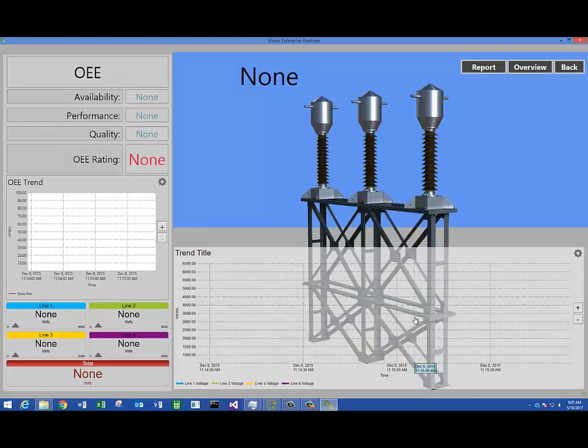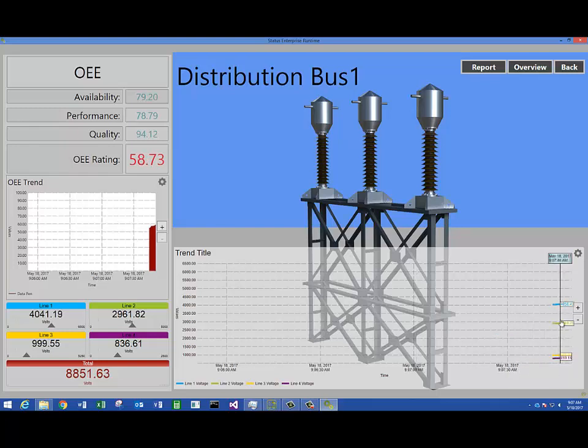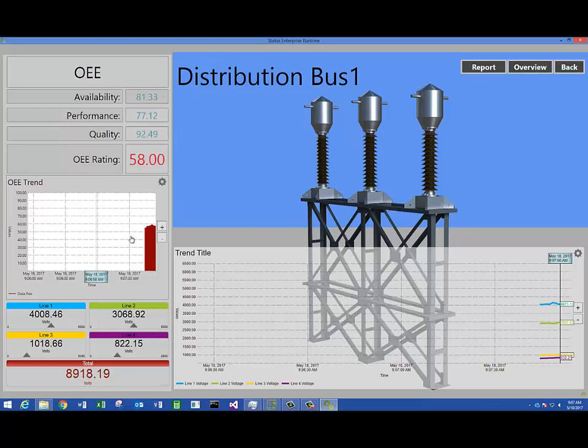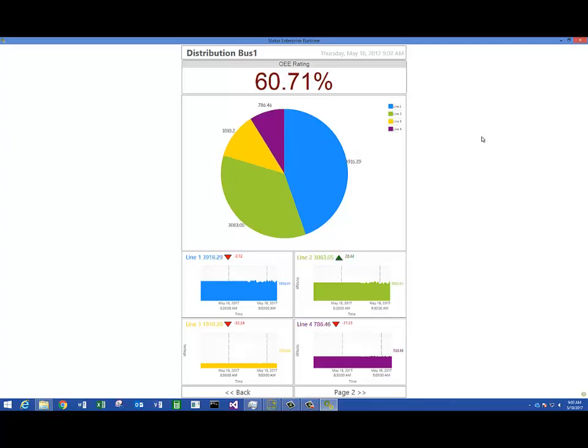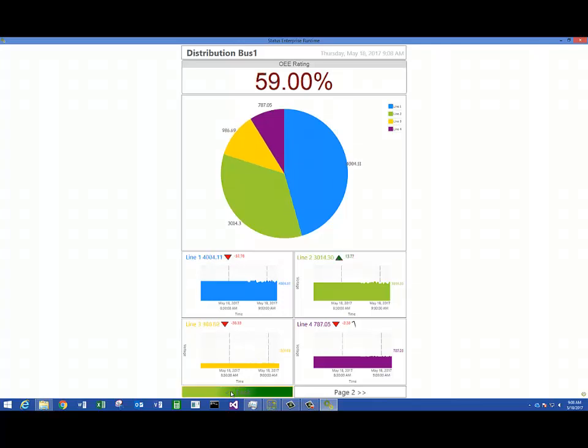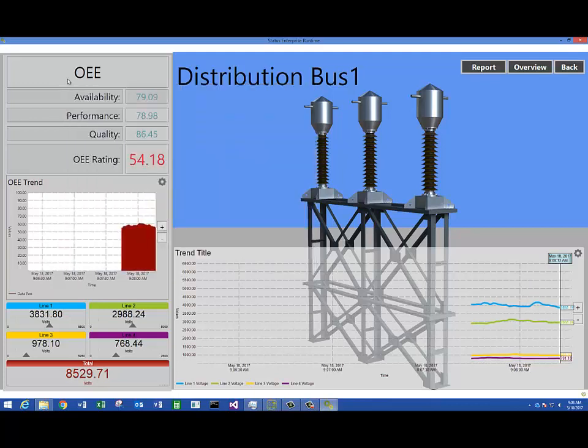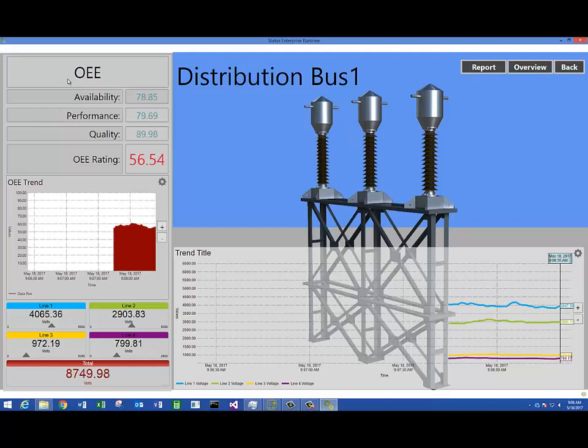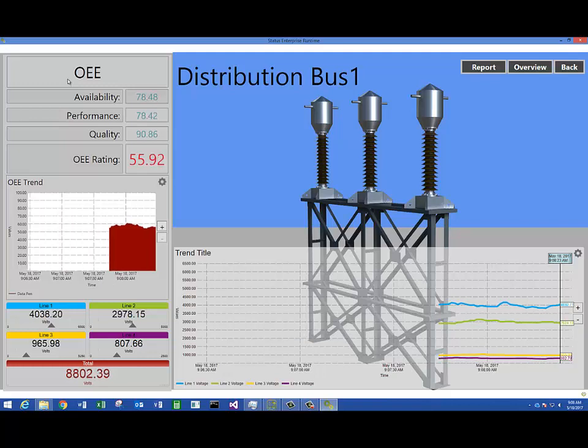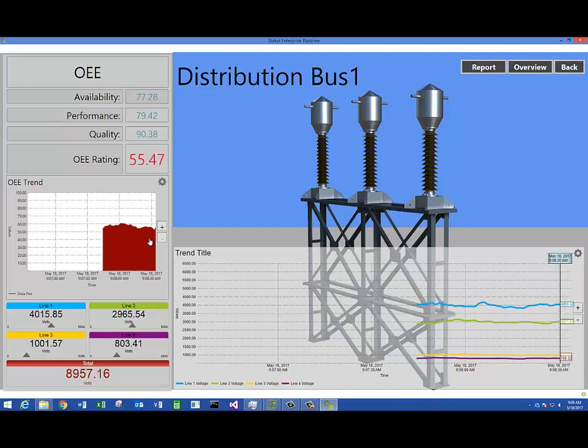I can click any one of these bubbles and drill down into it. Here I can see a trend running with four pens, and another trend on the left. I've got a report button — I can click that and it'll pull up a Mimic, and I can generate this Mimic as a PDF document and automatically email it to somebody if I choose. Going back to the top left, I can see a pop-up window with a calculated value. This is where we've used a calculation for creating the overall equipment efficiency rating, done by multiplying availability, performance, and quality together — an excellent example of how a calculation gets used in the system.